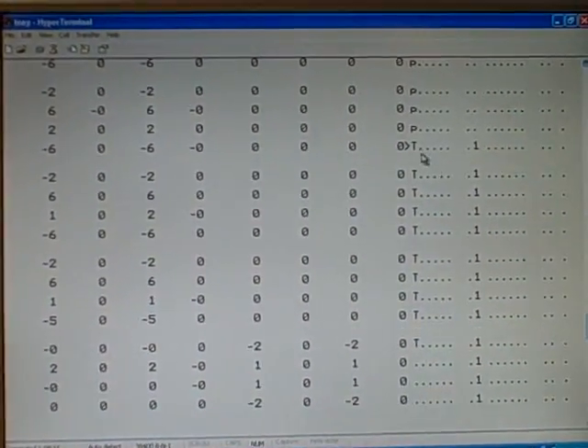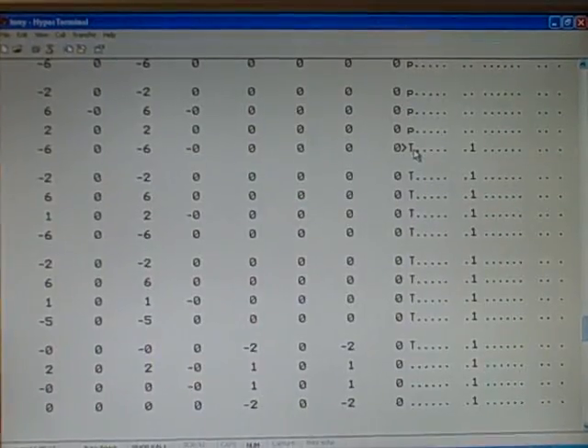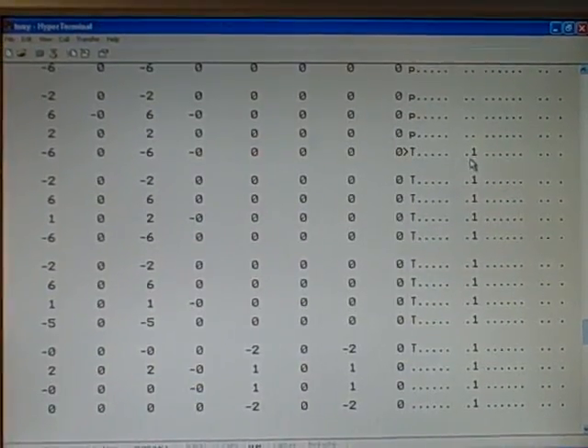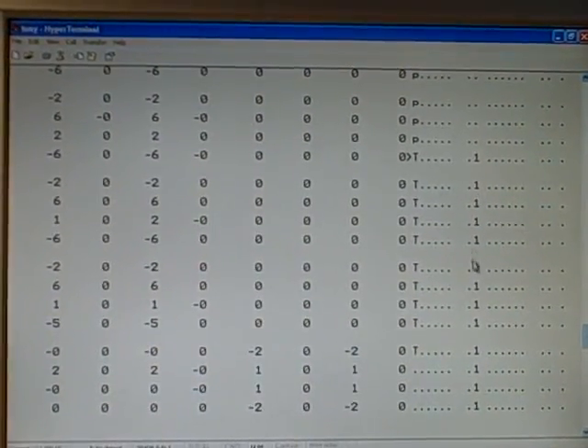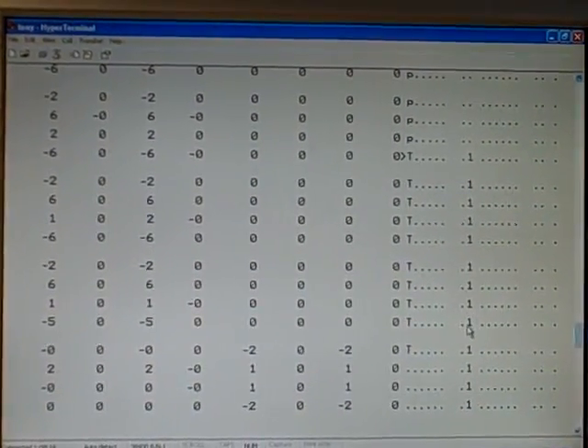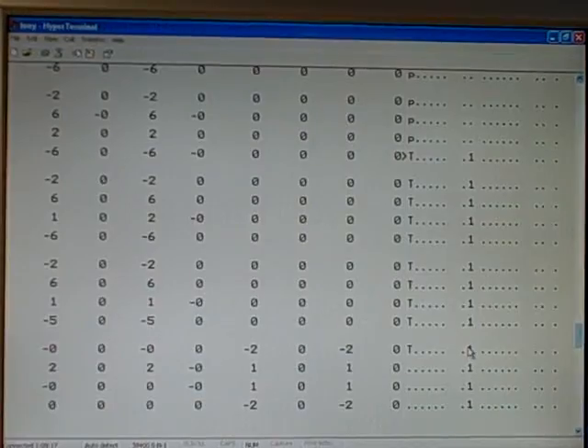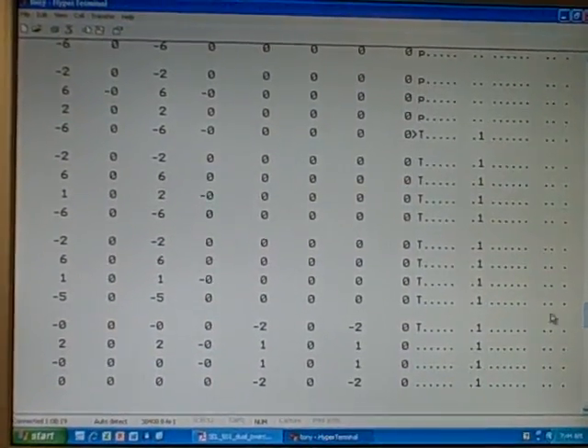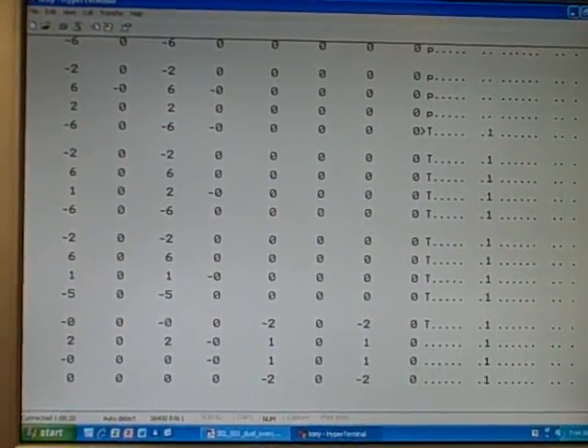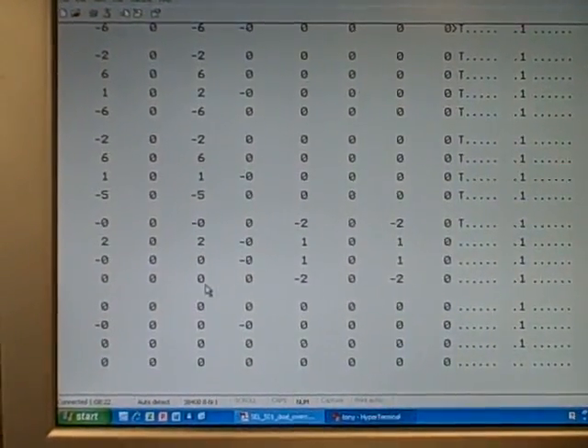So this is when the trip event took place. That's when the output contact was asserted, and it took a little over two cycles worth of time for the circuit breaker to actually open and interrupt the current through phase B.